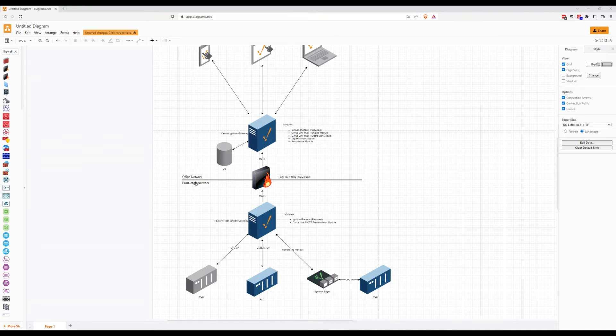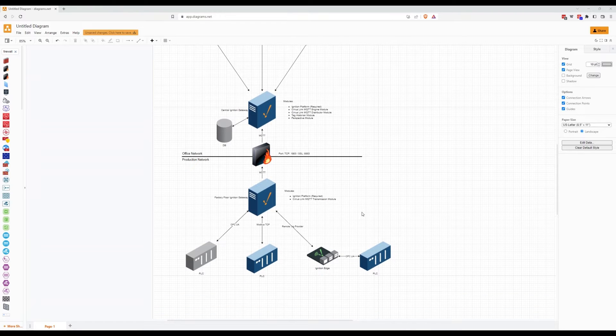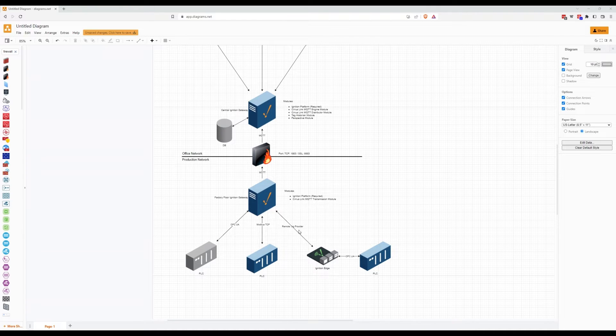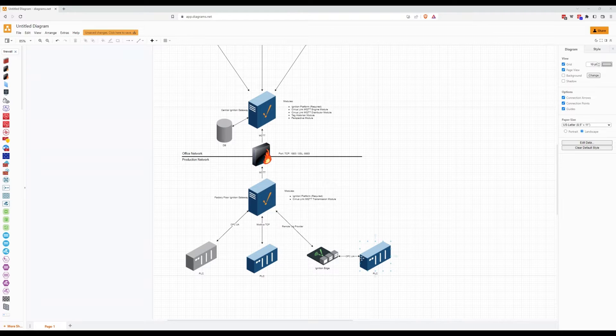We have two networks: the office network and the production network. On the production network we have a set of PLCs connected over OPC UA or Modbus TCP, or it could be a remote tag provider to an Ignition Edge device, which is then connected through OPC UA to a PLC or more PLCs.